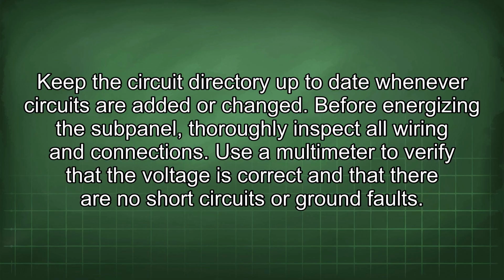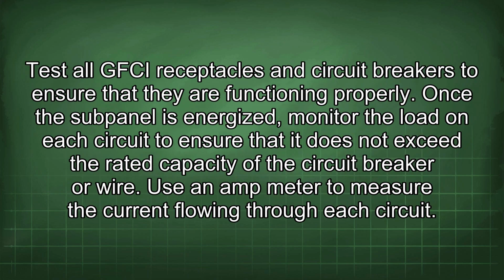Before energizing the subpanel, thoroughly inspect all wiring and connections. Use a multimeter to verify that the voltage is correct and that there are no short circuits or ground faults. Test all GFCI receptacles and circuit breakers to ensure that they are functioning properly.